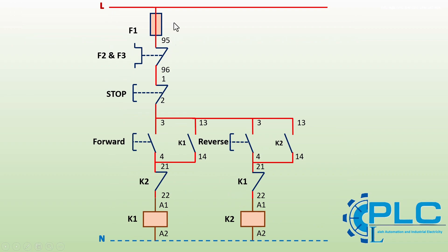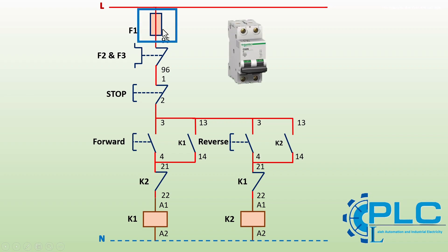Let's break down this circuit diagram step by step. Before wiring a control circuit, we must first design and draw its electrical diagram. This schematic helps us carry out the wiring process more easily and accurately. We will analyze the forward-reverse motor control circuit together, using standardized electrical schematics of various components that are universally recognized worldwide. The first component is the fuse — this is its electrical symbol, typically rated at 2A or 6A in control circuits.